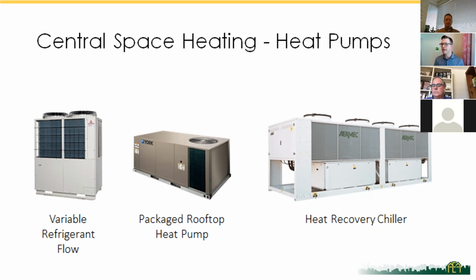You can also do packaged rooftop heat pump units, and have heat recovery chillers on the roof. A heat recovery chiller is the most sophisticated version of doing heating and cooling in a central application with a heat pump. These systems can supply hot water and chilled water for heating and cooling, and also domestic hot water. However, these are pretty highly engineered systems.